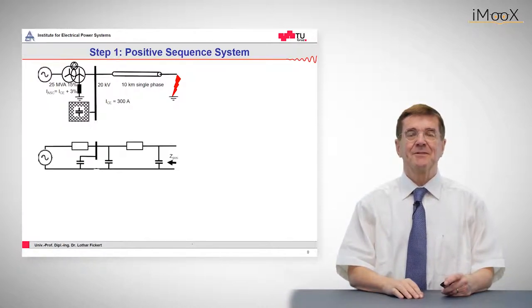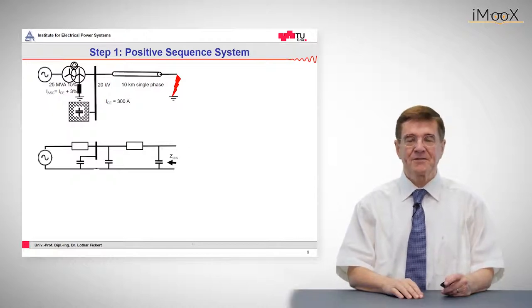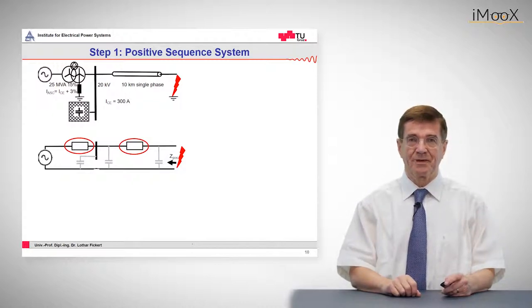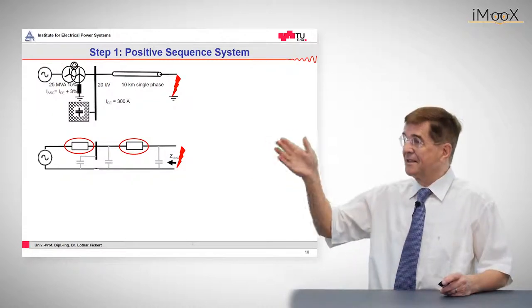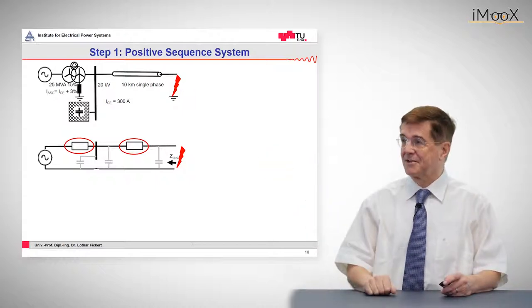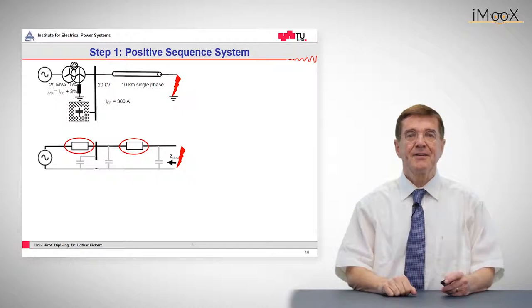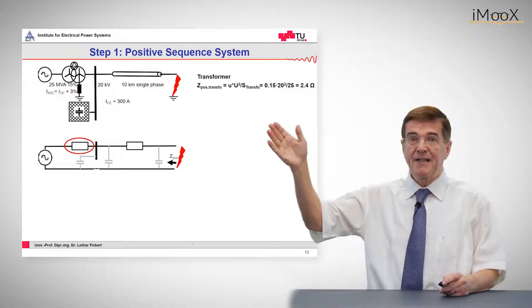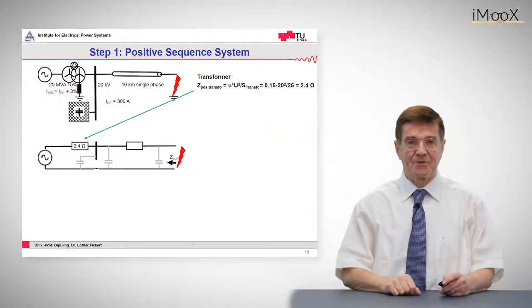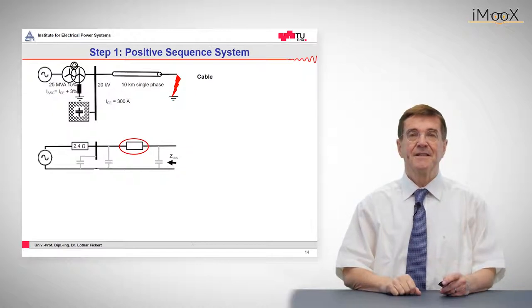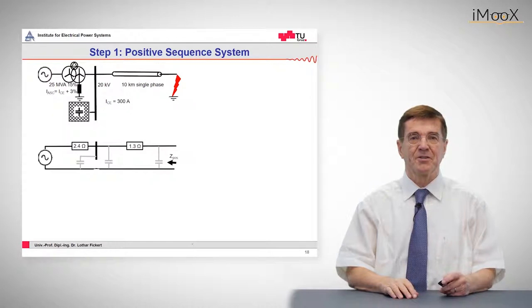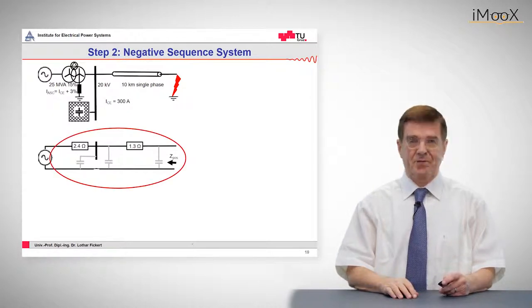Now let's start with the positive sequence system. The positive sequence system is known to everybody because a three phase short circuit is controlled by the vital elements of this three phase system, which is the transformer impedance and the line impedance. The transformer impedance can be calculated as shown above and the value is 2.4 ohms. The same applies to the line impedance. The line impedance is the specific impedance of the line multiplied with the length of the line, and that comes out as 1.3 ohms.